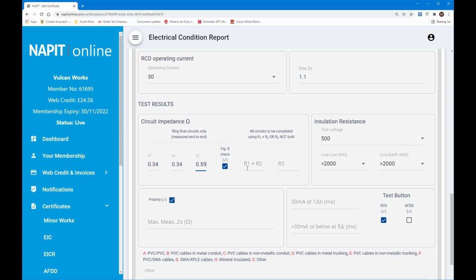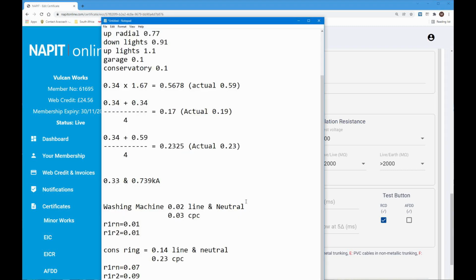Now you don't have to actually put down the R1RN reading, it's only the R1R2. But I did the R1RN because you do that to do the figure of 8 to prove everything is working. So the R1RN value calculated was 0.34 plus 0.34 divided by 4. So the calculated value should have been 0.17. The actual reading was 0.19. Absolutely fine. And then the reading we're going to put down on the form is 0.34 plus the 0.59, which is the reading we got here for the CPC, divided by 4. So the calculated reading should have been 0.2325. The actual reading was 0.23, as you saw in the video.